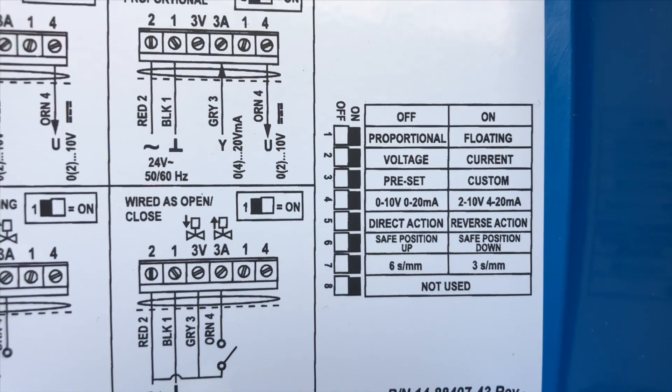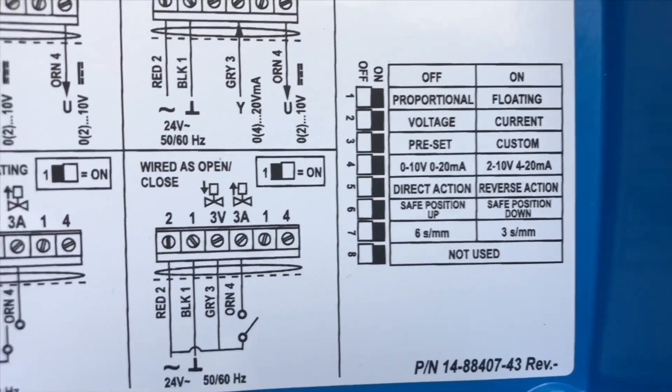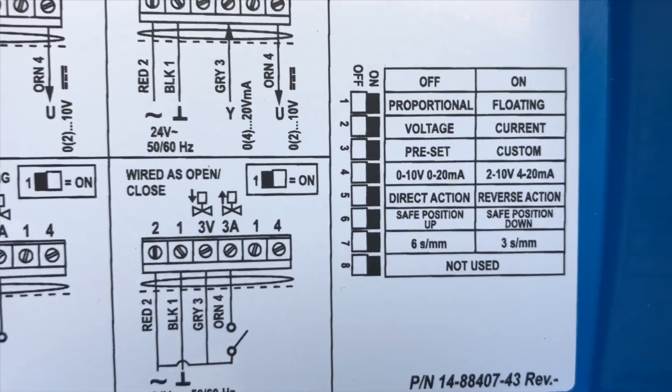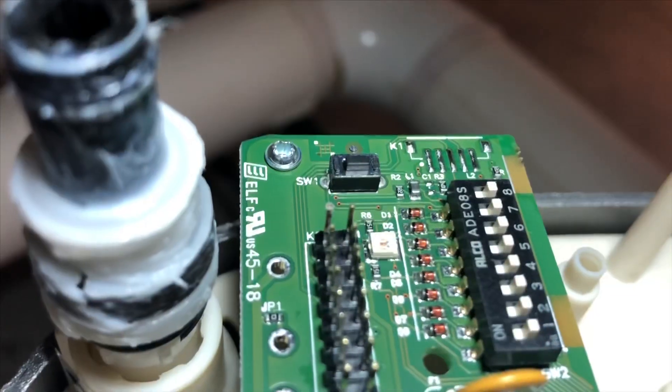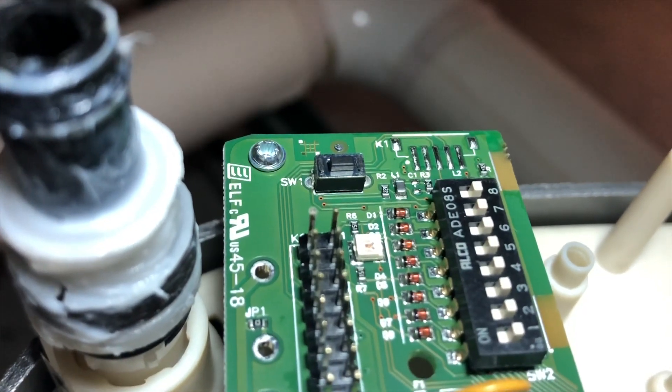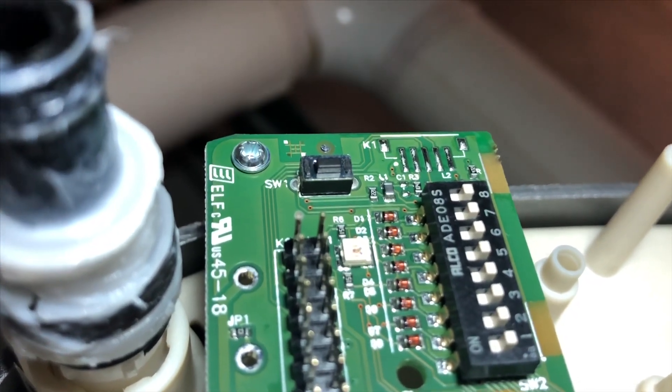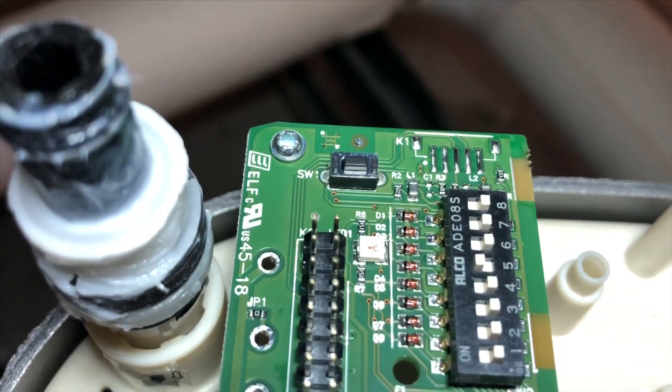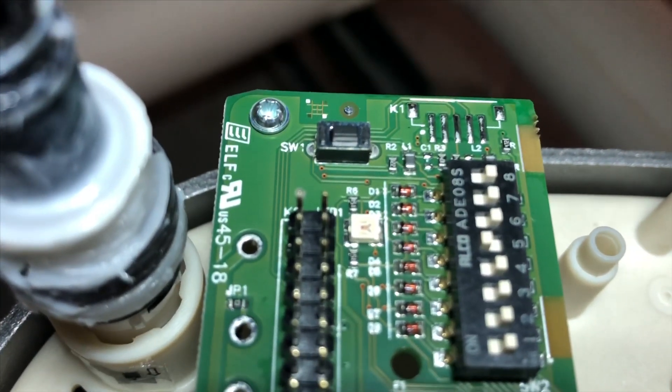So we're going to go to reverse action on, which would be number 5, dip switch number 5. We're going to switch that. We've turned our power off to our controller. And we're going to switch dip switch number 5 to on. Now we've put it to the on position, dip switch number 5, which will be reverse action.